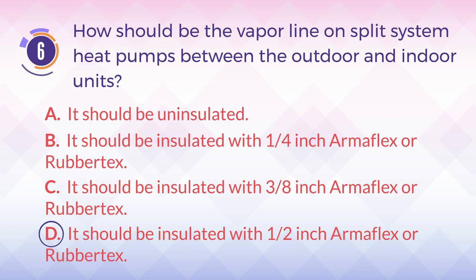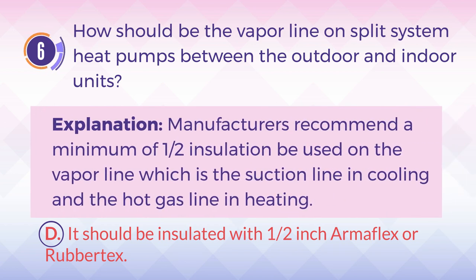The answer is D. It should be insulated with 1/2-inch Armaflex or Rubbertex. Explanation: Manufacturers recommend a minimum of half-inch insulation be used on the vapor line, which is the suction line in cooling, and the hot gas line in heating.